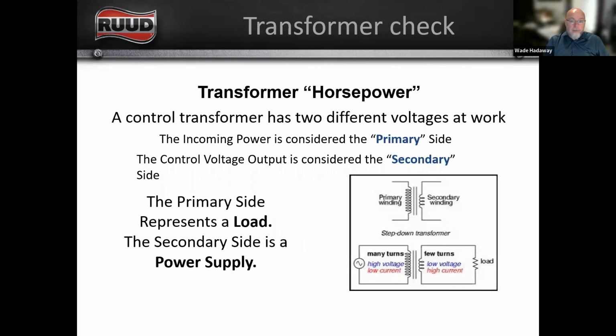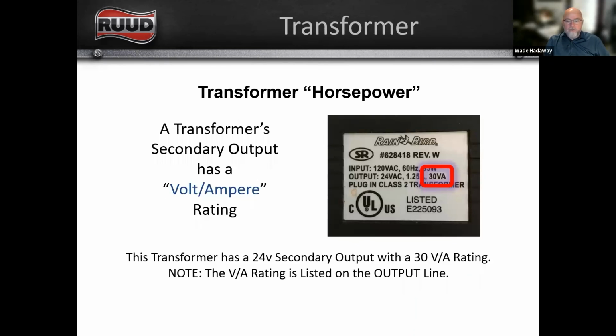So again, our incoming power is our primary, and our control voltage, or output side, is the secondary. If we look on the data plate, or the information on the transformer, you can see your input and output ratings, right? So this particular transformer has a 30 VA rating, or a 30 volt-amp rating. We'll talk about exactly what that means on the next slide. So this is a 30 VA transformer.